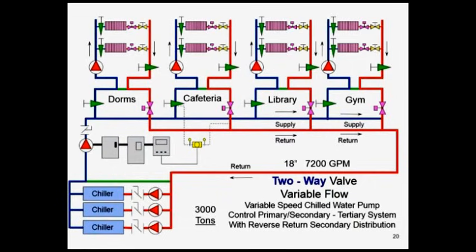I drop my main back from 20 to 18 inch. I drop my total flow rate back from 9,600 GPM to 7,200 GPM with 2-way valves. Man, I'm saving a lot of first cost. I got a lot of good energy savings going on. But now, how do you balance? You begin to get the point.